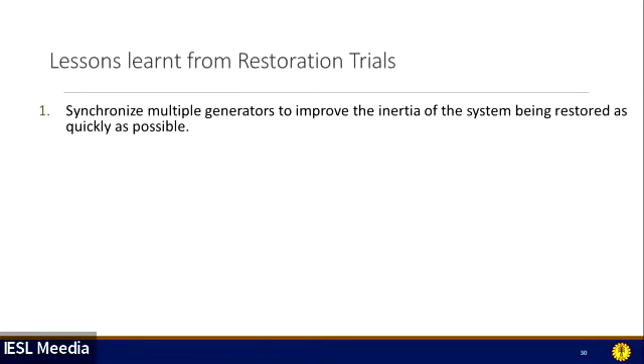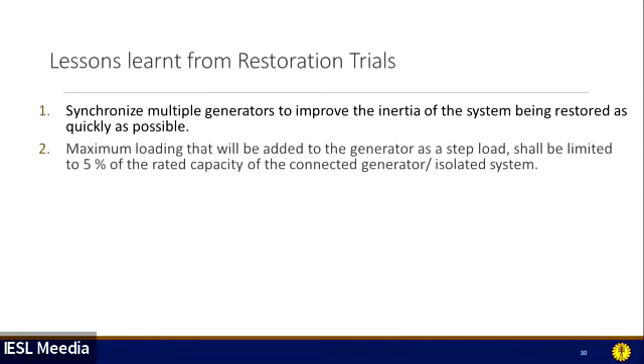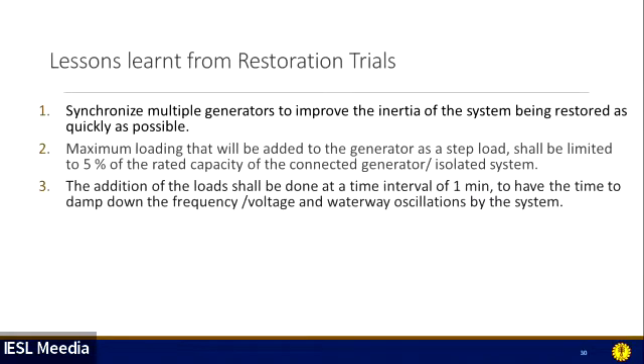Synchronize multiple generators to improve the system inertia as quickly as possible during the initial phase of the restoration, that is, to improve the inertia of the system being restored. What we usually do is start a generator and energize a 33 kV feeder with a load. That has to be done carefully, because if the load added is too much, the frequency drops significantly, and if the generator cannot tolerate that frequency, it trips again. To avoid that, we came to a norm that the step load added to the generator at the initial phase shall be limited to 5% of the rated capacity of that particular generator or the isolated system. So it worked well in this case.